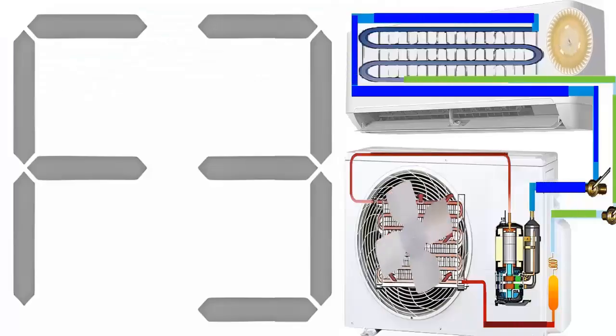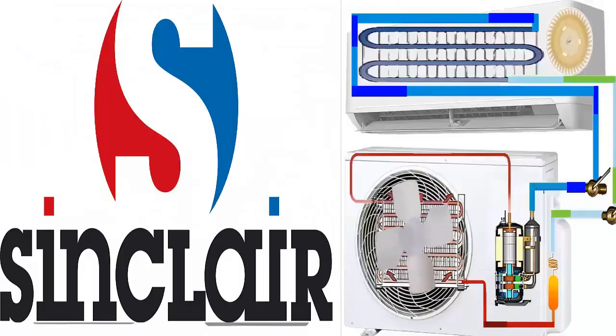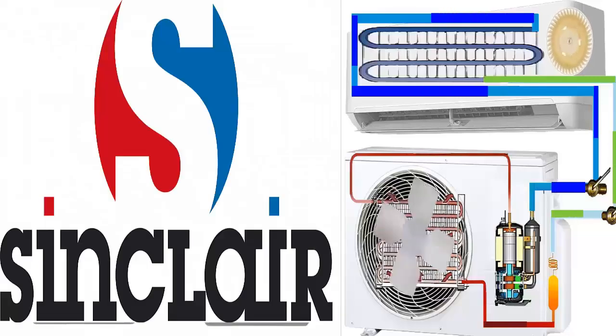Code F3 indicates problems with a sensor located near the coil of the outdoor unit, specifically attached to the grill. This sensor measures the temperature of the air sucked in by the outdoor unit's fan to average the outside air temperature. This code is triggered when the sensor is open or short-circuited.